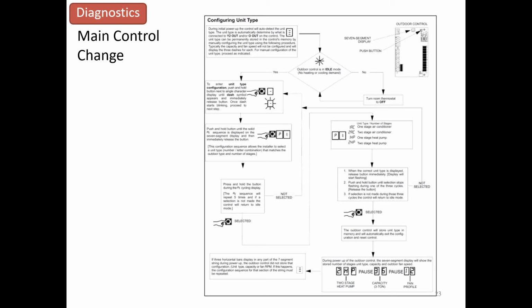There's a 7-segment display outside in the outdoor unit. When you push the buttons on it, the recall button, it will actually come up and we'll walk through 3 or 4 different cycles that are available to you. If it's programmed, then it's going to accept the programming that is there and it's going to start letting you know what's going on. So it's going to display the outdoor liquid line temperature, outdoor ambient temperature, and what position that it's running in, heat pump or AC. And then the next thing it's going to tell you is what capacity it's running at. It might be 53%, and it will let you know what the compressor is running at.